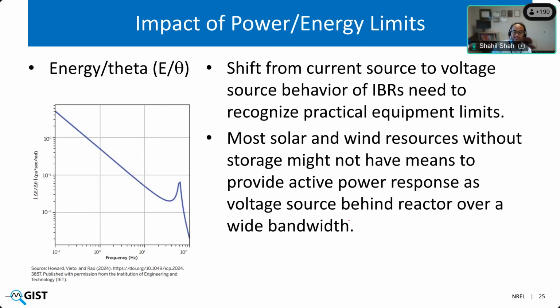Here is one slide which really shows why we need to keep these limits sometimes more relaxed. So here is the transfer function from energy to theta. So instead of P by theta, it is E by theta. Energy, as you know, is the integral of active power. So a flat gain in P by theta would give us this type of single order pole type of response, where the gain would be very high at low frequencies.